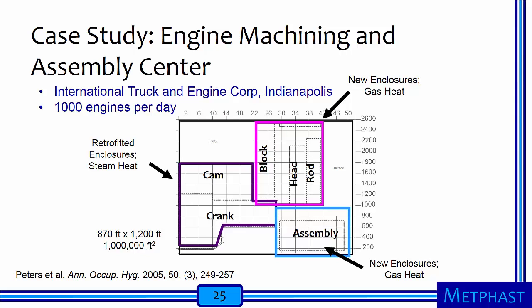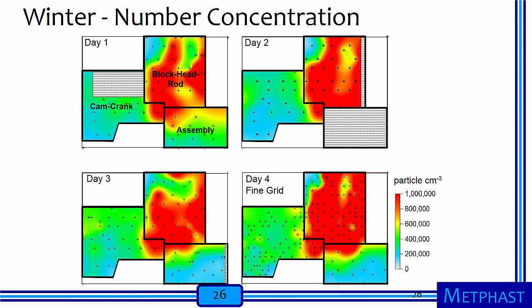I will now show a published case study demonstrating the importance of using different instruments to assess airborne exposures. Hazard mapping was performed at an engine machining and assembly center of International Truck and Engine Corporation in Indianapolis, Indiana. This facility consisted of roughly 1 million square feet — equivalent to 30 football fields — under a single roof. The facility had poorly fitting retrofitted enclosures and steam heat in a cam crank production area, while new enclosures with gas heat were used in a blockhead rod line and an assembly area. In winter, we measured particle number concentrations with a condensation particle counter throughout the facility on four consecutive days.